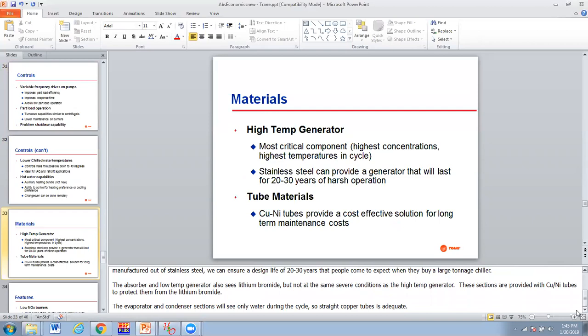The absorber and low temperature generator see lithium bromide, but not as severe conditions of high temperature as the generator. These sections are provided with copper nickel tubes to protect them from the lithium bromide, and the evaporator and condenser sections see only water, so standard copper tubes are adequate there.